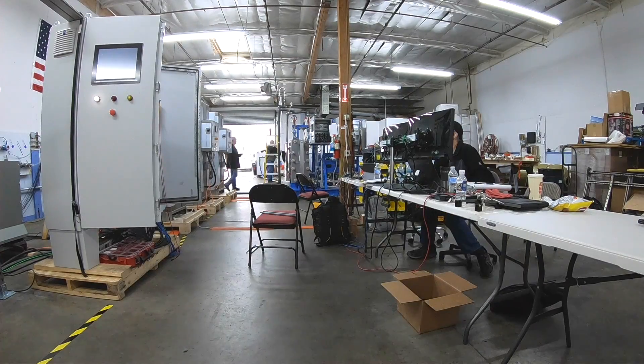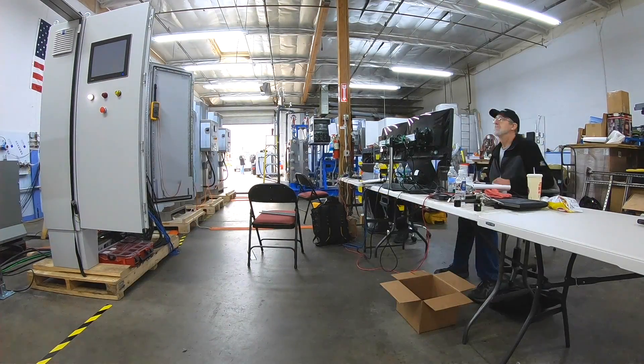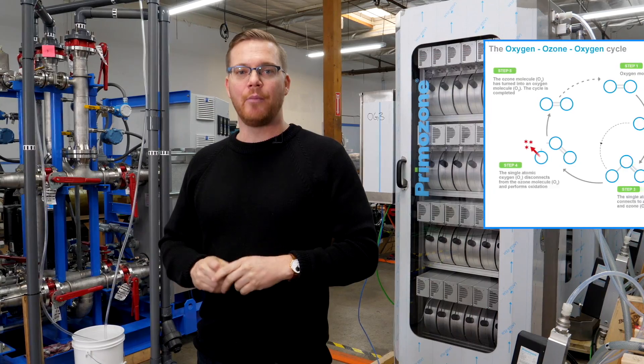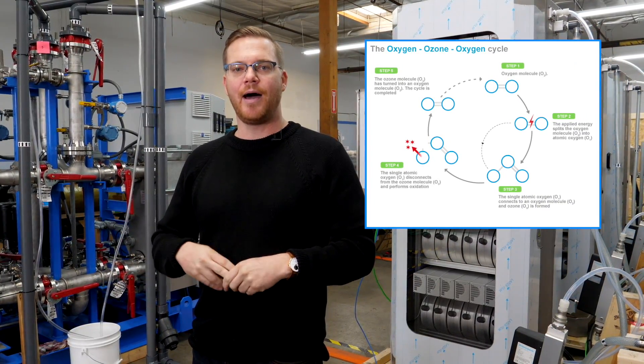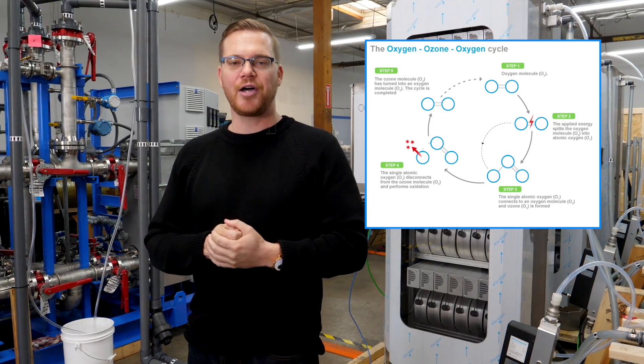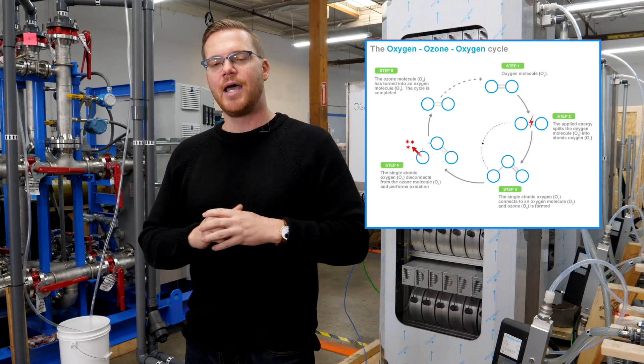The commissioning of their new ozone system must be flawless or we risk losing an entire population of aquatic species. Ozone is one of the strongest oxidants on the planet, and we're creating it using the corona discharge method, where we apply high-voltage electricity to high-concentration oxygen, breaking the O2 molecule so it reforms as O3.